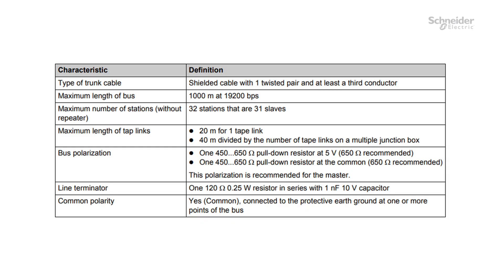There may be additional cabling rules according to the fieldbus used. For example, using PROFIBUS, CANOPEN, or MODBUS, you must check the line terminator, the length of the bus, and the number of slaves. For more information, please refer to the guide for each module on www.se.com.